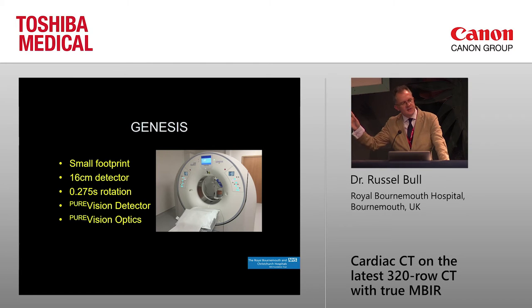This is the Toshiba Aquilion One Genesis. It's a small scanner with a small footprint — only the same size as most 64-slice scanners. But it has a big, wide 16-centimeter detector, so it can cover the whole heart in one heartbeat and never needs multi-heartbeat acquisition. It has the fastest rotation at 0.275 seconds, so the temporal resolution is good.